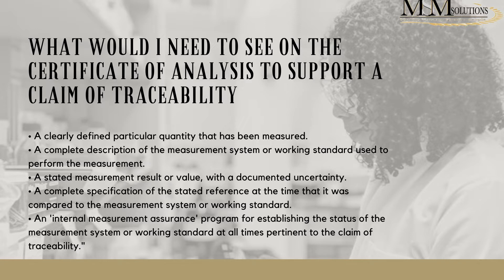So if you were to buy a CRM, what do you need to look out for to support the claim of traceability? The main difference between the two is metrological traceability with respect to CRM. What you need to look out for is a clearly defined particular quantity that has been measured, a complete description of the measurement system or working standard used to perform the measurement, a stated measurement result or value with a documented uncertainty, a complete specification of the stated reference at the time it was compared to the measurement system or working standard, and an internal measurement assurance program for establishing the status of the measurement system or working standard at all times pertaining to the claim of traceability. Remember, you need an unbroken chain when it comes to traceability, so you need to see how that traceability has been transferred through.